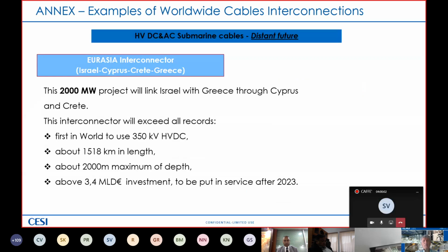Talking about Cyprus, why? Because there is a project already financed, the so-called Euro-Asia Interconnector: Israel, Cyprus, Crete, Greece, and from Greece to Italy and the rest of Europe. This is a 2,000 megawatt project, and this interconnection will exceed all records. First in the world to use 350 kV HVDC. About 1,500 kilometers in length, about 2,000 meter maximum depth, and above 3.4 billion euro investment, to be put in service after 2023.